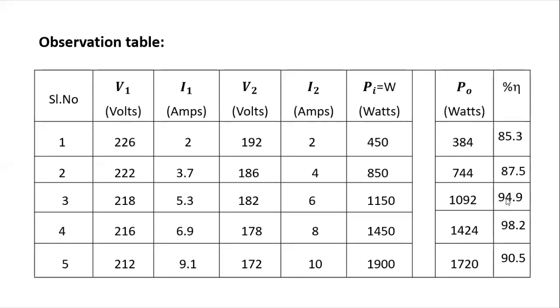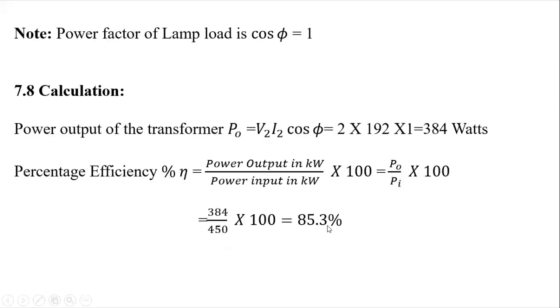From the readings, we can observe that the maximum efficiency occurs almost when the current is equal to 80% of the load current. From this we can conclude that the maximum efficiency of the transformer is achieved when the load current is 75 to 80% of the rated current. So this is how we conduct the experiment on a single phase transformer and calculate the efficiency of the transformer for different load conditions. Thank you.